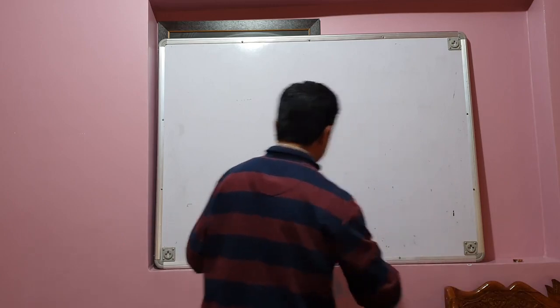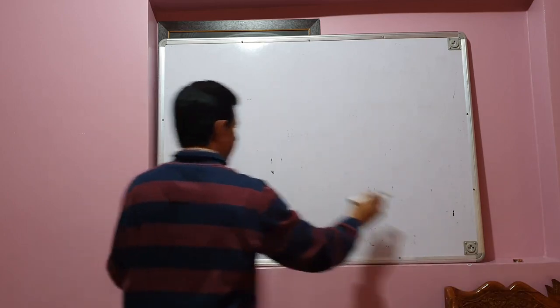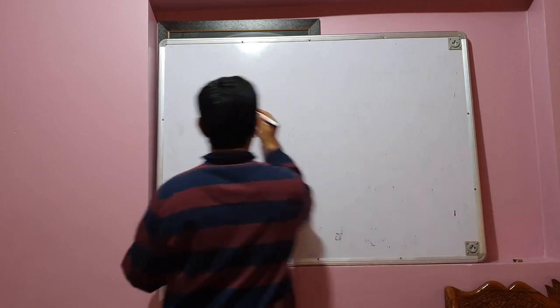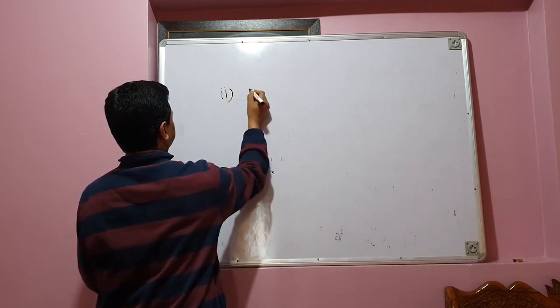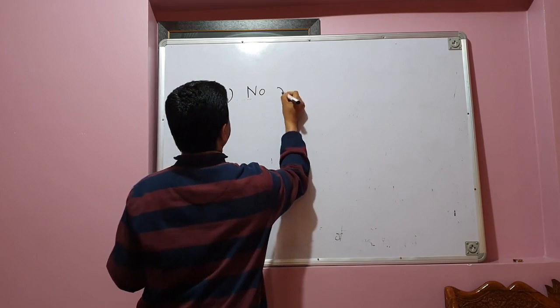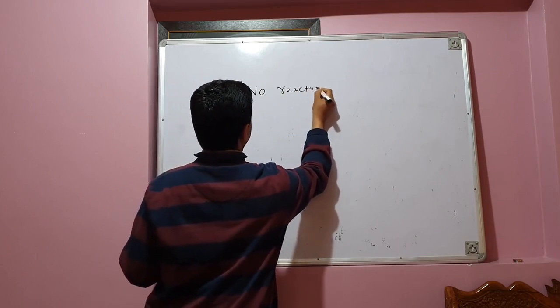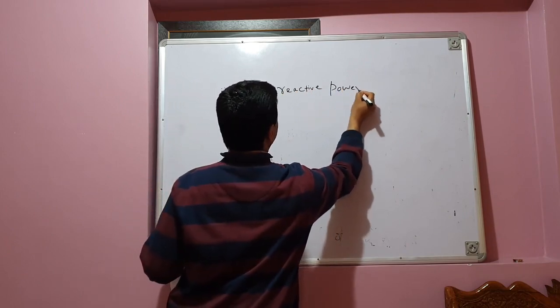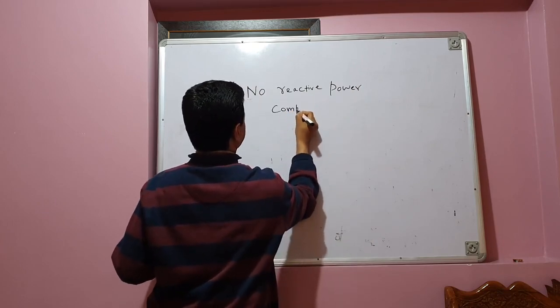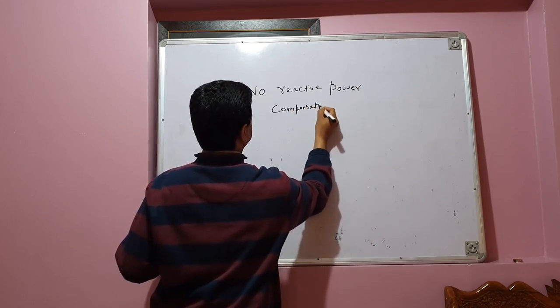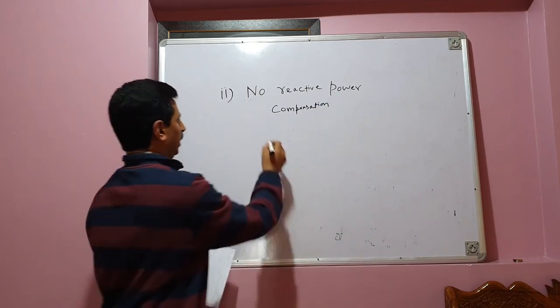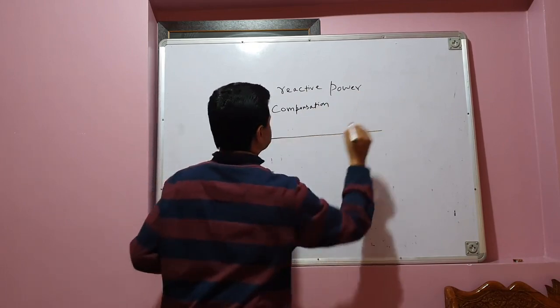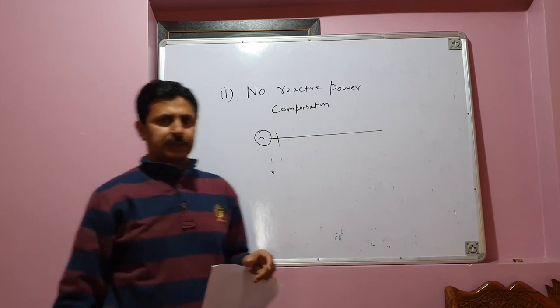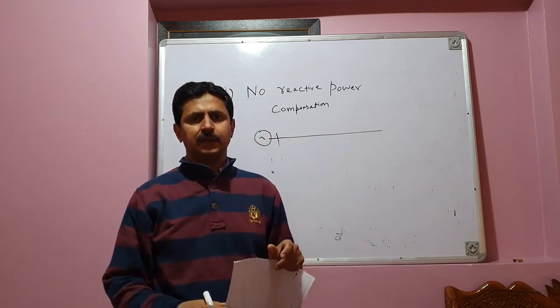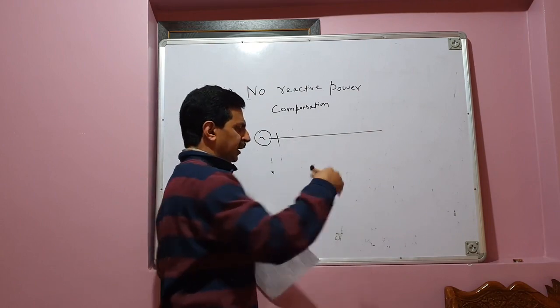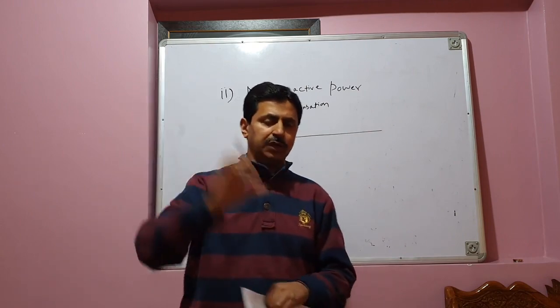What is the second advantage of transmitting power over DC, over AC? Second advantage: no reactive power compensation is required. No reactive power compensation is required in DC transmission. See, if you are transmitting power over AC, the AC line has got reactance, and you need to compensate, and then there is the flow of reactive power over the AC transmission line.